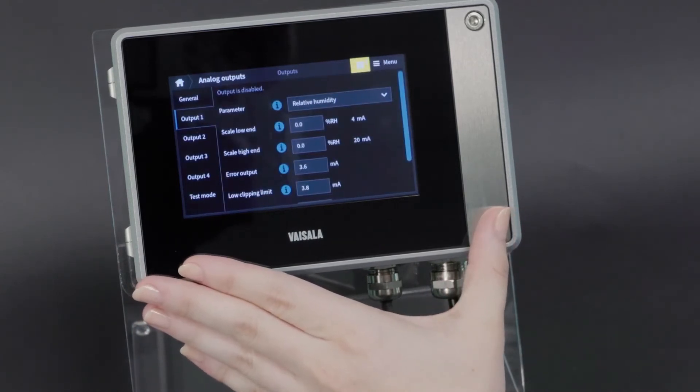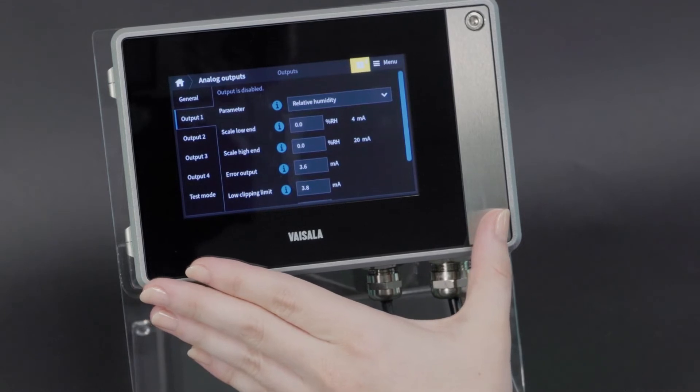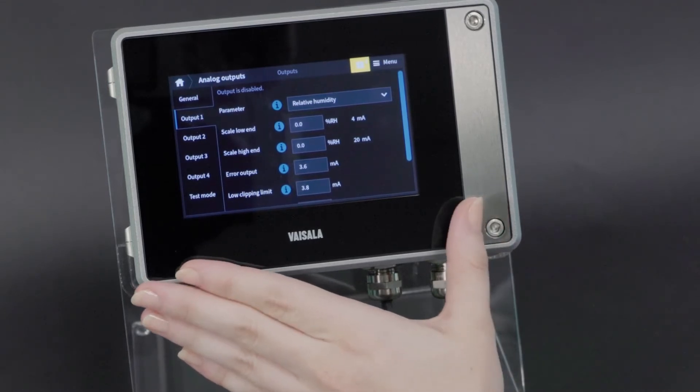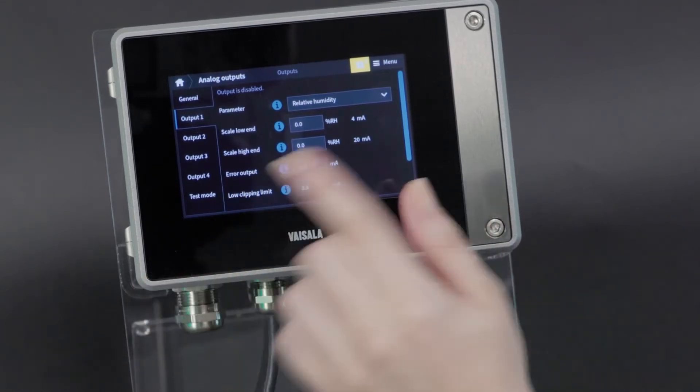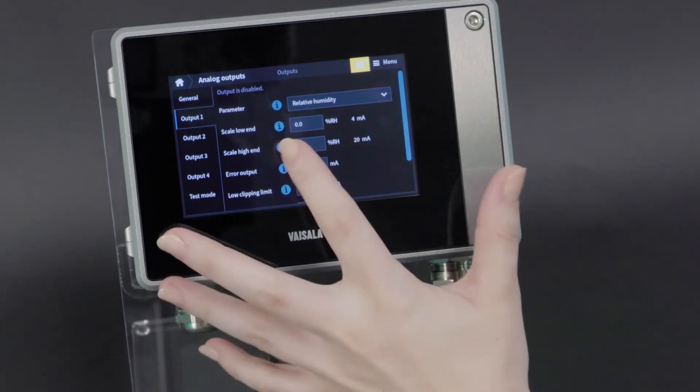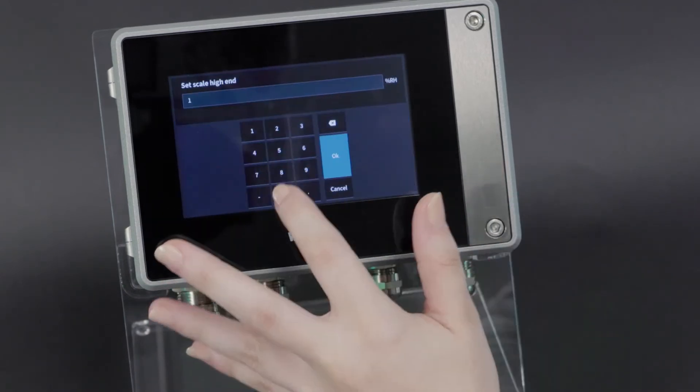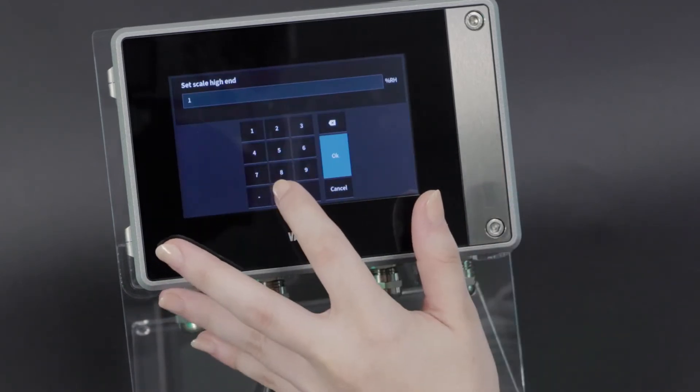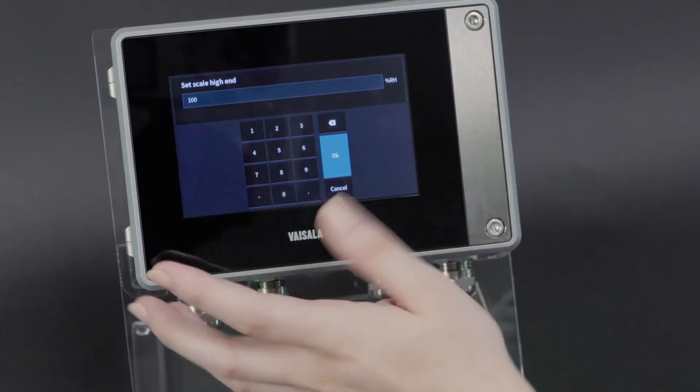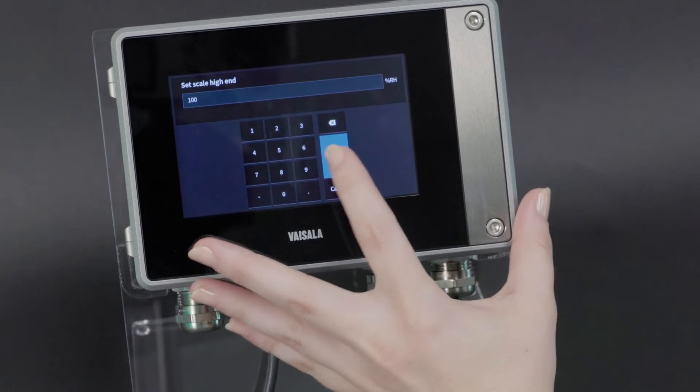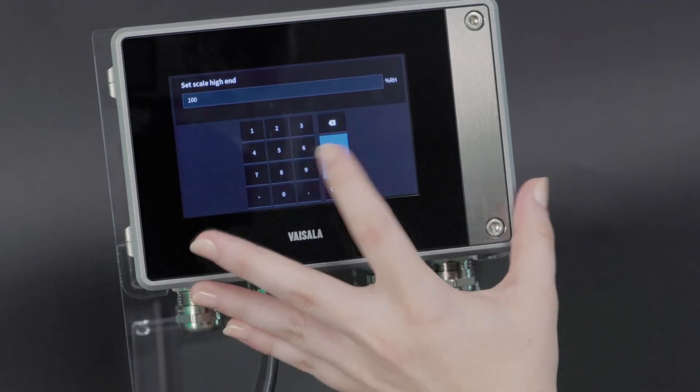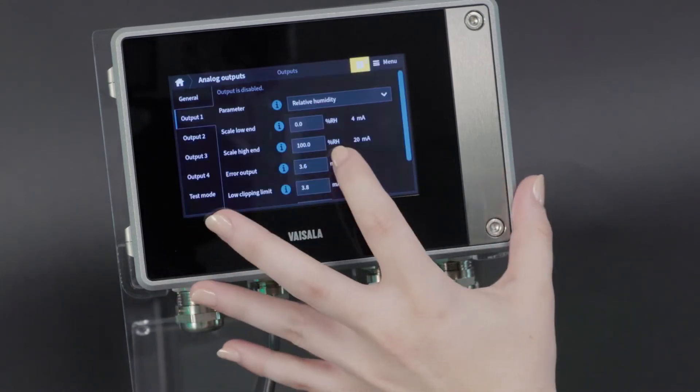Now we need to arrange the scaling. Pretty standard scaling for humidity would be 0 to 100%. We already have the low end of 0, so I'll just change this to 100%. And you can see the label over here so that if we were doing temperature, you know whether you're working in Fahrenheit or Celsius.